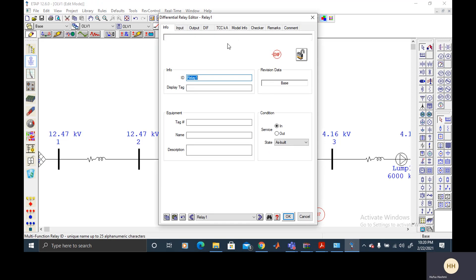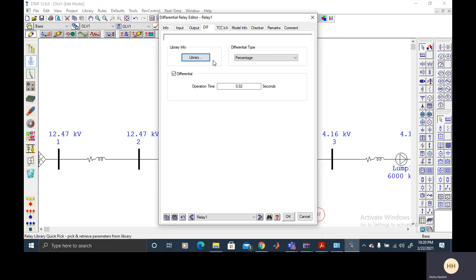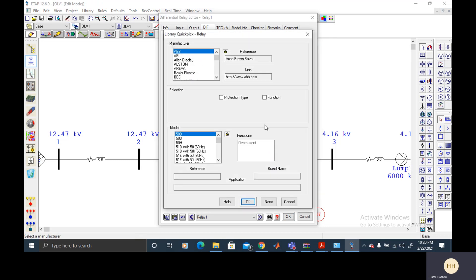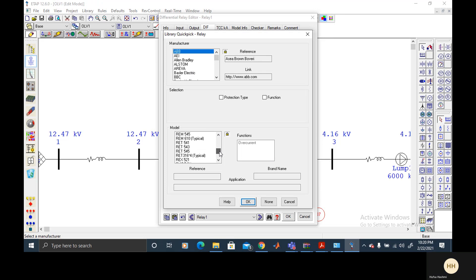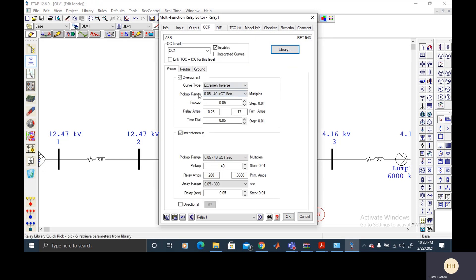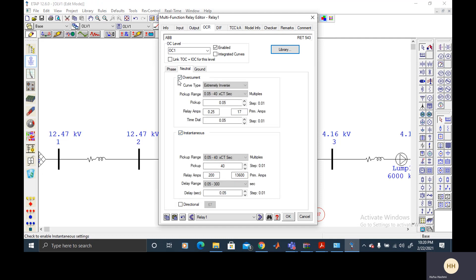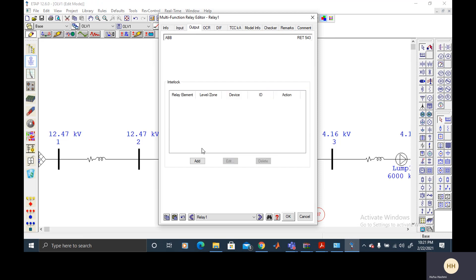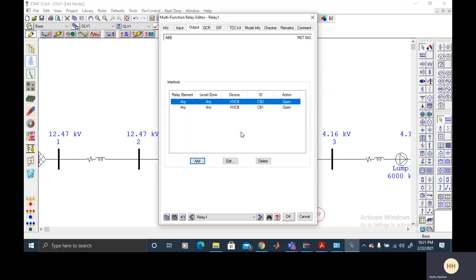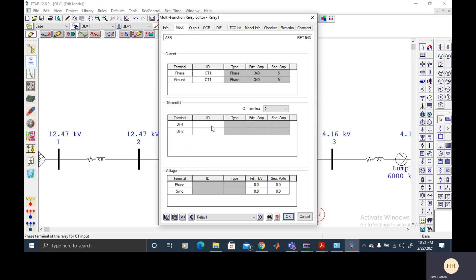And then I will have to do the differential relay. First I'm going to click on this DIF and from library I would select a relay that has got a function of differential in it. So the relay is RET 543 that has got differential in it. And I don't want overcurrent protection so I would deselect it. So I'm deselecting it and from output I would add the circuit breaker that I would want to trip. That is circuit breaker 1 and then circuit breaker 2. And the other thing is from the input I would select CT1 and CT2. These are the two inputs of the differential relay.